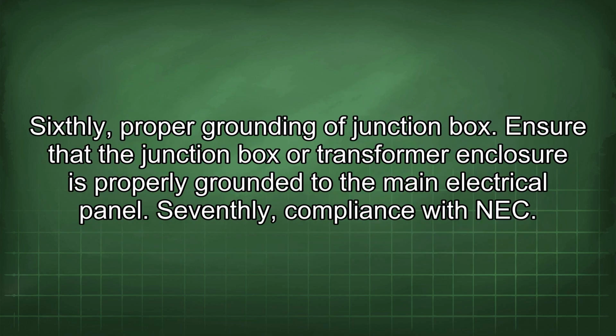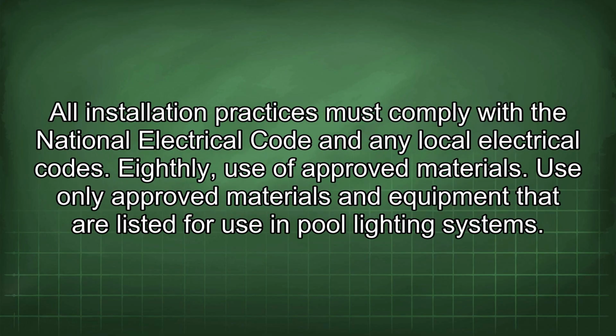Fifthly, protection from damage. Protect the #8 American wire gauge EGC from physical damage during installation and backfilling. Sixthly, proper grounding of junction box. Ensure that the junction box or transformer enclosure is properly grounded to the main electrical panel. Seventhly, compliance with NEC. All installation practices must comply with the National Electrical Code and any local electrical codes. Eighthly, use of approved materials. Use only approved materials and equipment that are listed for use in pool lighting systems.